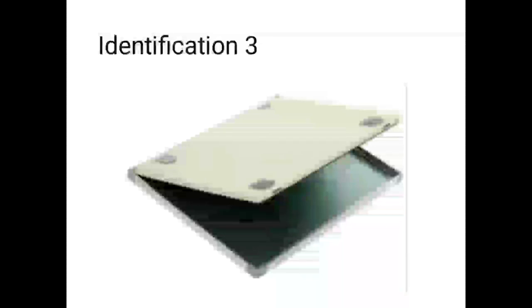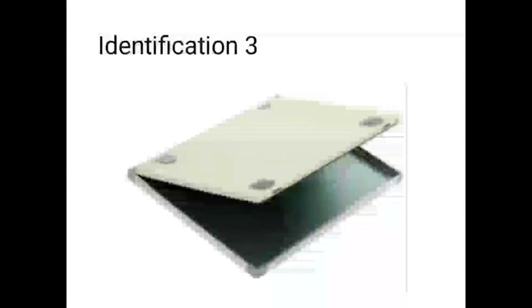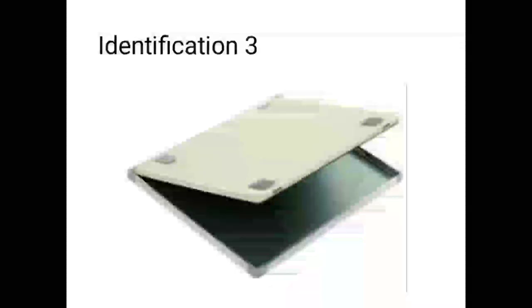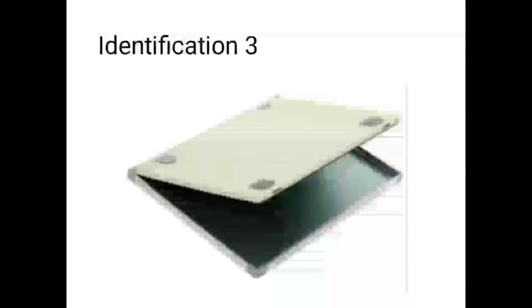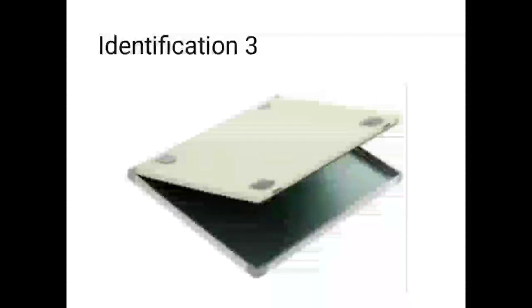This is a cassette showing the back side. The back side of the cassette is made up of lead. What is the purpose of the lead in the back side of the cassette? The purpose of the lead is it prevents back scattered radiation. The cassette front side will have low atomic number materials like cardboard or plastic.